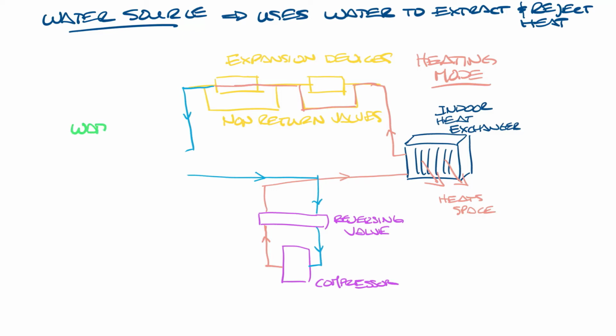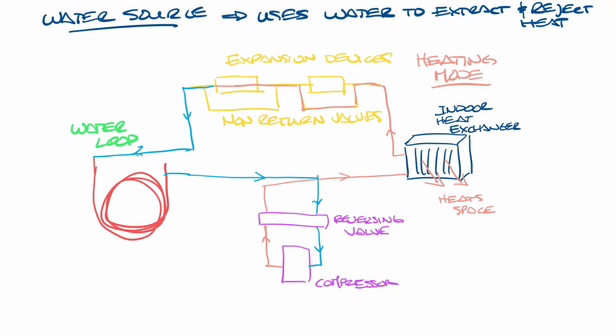This is usually done by having a coaxial heat exchanger that has the refrigerant run on the inside of the tube and a water loop run on the outer tube. So let's connect the refrigerant to our water loop. And then let's connect a water in and a water out to our water loop. During cooling, the lower water temperature draws the heat away from the compressed hot gas of the refrigerant. In heating, which is the mode that is shown in this drawing, the refrigerant draws the heat from the building water loop and exits as warm temperature, low pressure gas.